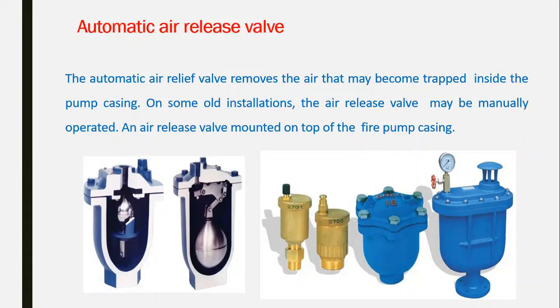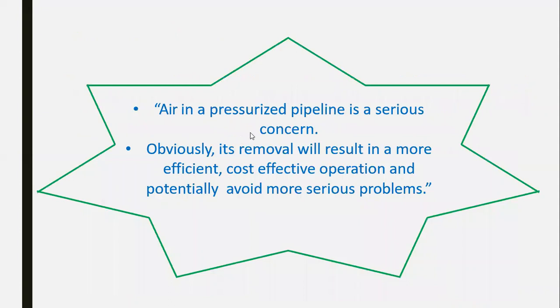So it could be on the pump, or on the common riser, on the horizontal, not the vertical. Vertically, it will not operate, so it has to be on the horizontal pipes. The air in a pressurized pipe is a serious concern. Its removal results in more efficient, cost-effective operation and potentially avoids more serious problems, which we'll talk about: rusting, hammering, and turbulence in the network.